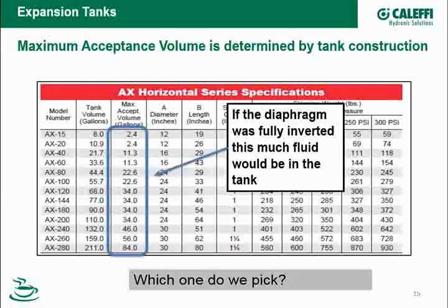A couple of questions, Jody. Is there any downside for someone selecting an expansion tank that is oversized? Oversizing is an excellent question. We'll actually see this when we start to get into the sizing process. But if I'm doing a commercial system, typically I'm going to do what's called a critical sizing. I'm going to try and find the right expansion tank that gives me the best combination of volume and performance.